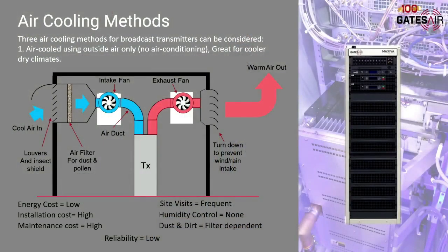Okay? Humidity control. Electronic devices, as you know, right? You've got to control the humidity. You don't want condensing moisture in an amplifier, and those fins will condense moisture. So how do you control the humidity when you're drawing air from outside? It's great if you're in an environment like the desert where you've got a dry environment, but if I'm in Canada or I'm in Maine, well, guess what? Try to control the humidity there. Or Florida, for example. That's even worse. Now you've got a hot, humid environment. Trying to control the humidity in that kind of environment is almost impossible.